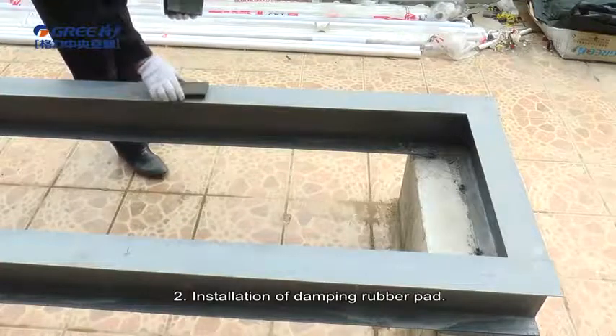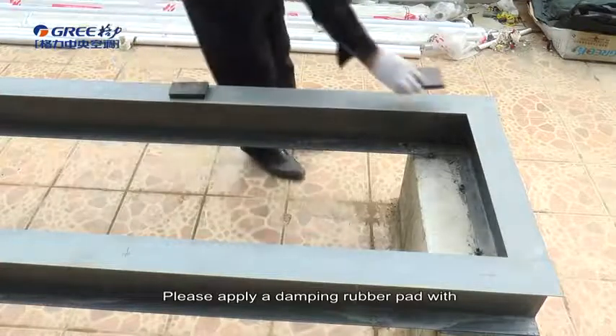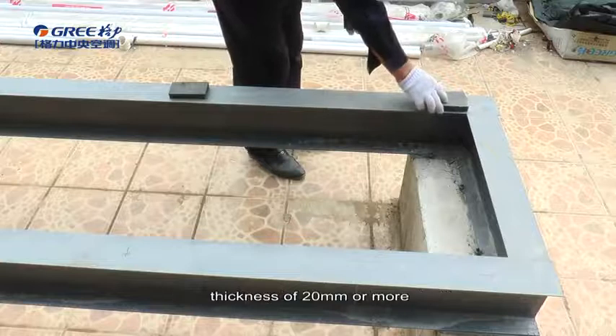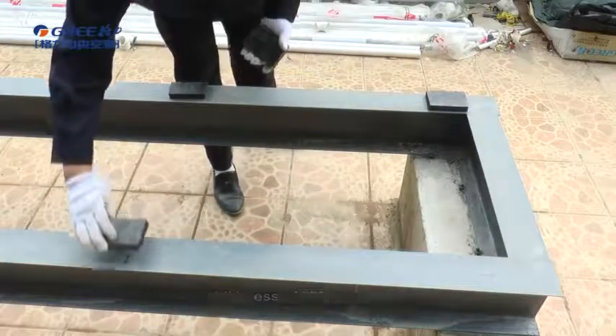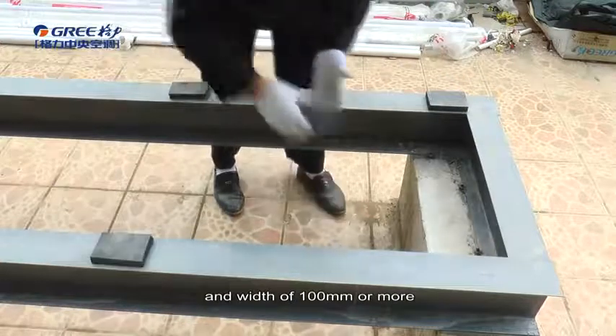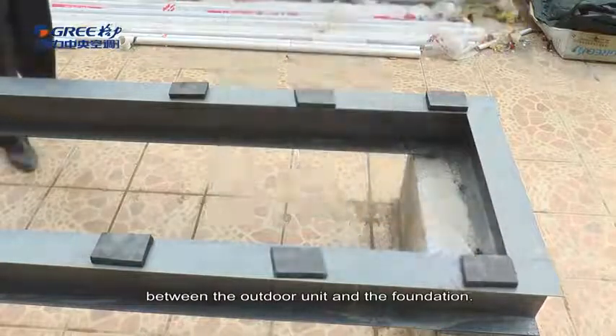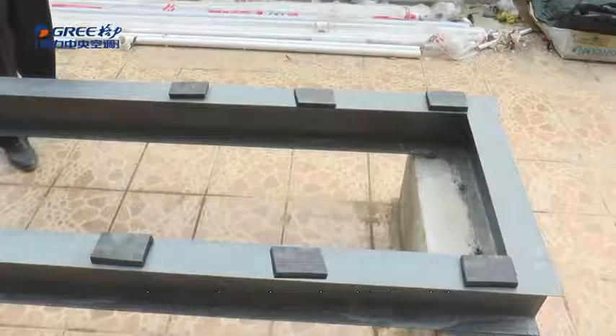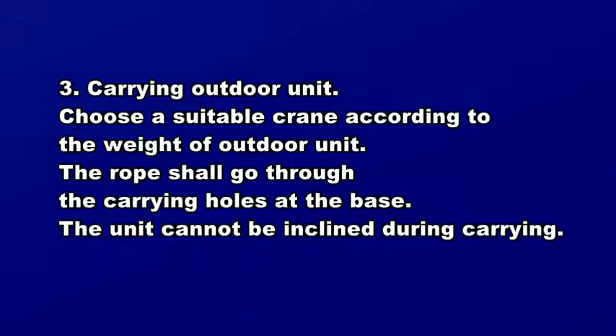Second, installation of damping rubber pad. Please apply a damping rubber pad with thickness of 20 mm or more and width of 100 mm or more between the outdoor unit and the foundation. Third, carrying outdoor unit. Choose a suitable crane according to the weight of outdoor unit. The rope shall go through the carrying holes at the base. The unit cannot be inclined during carrying.